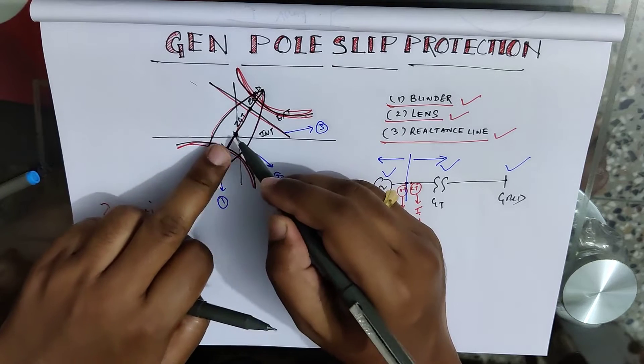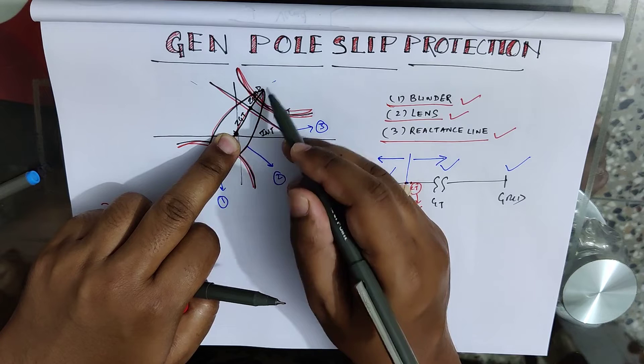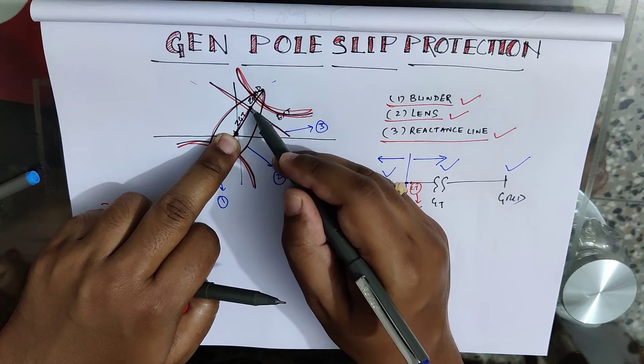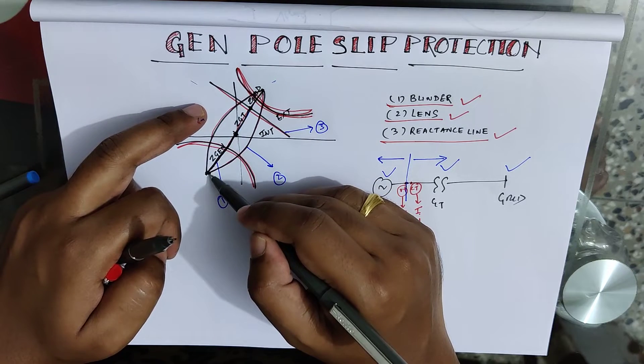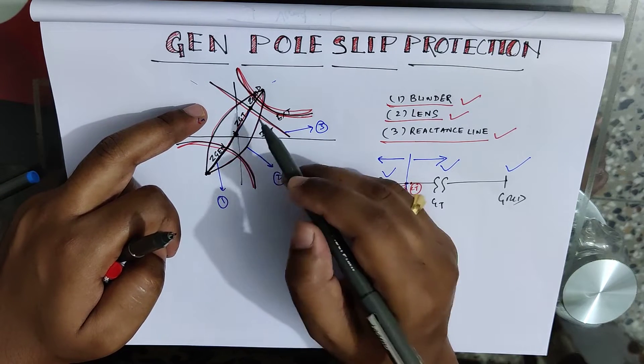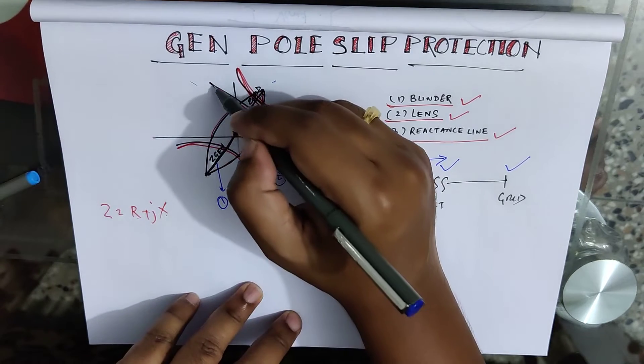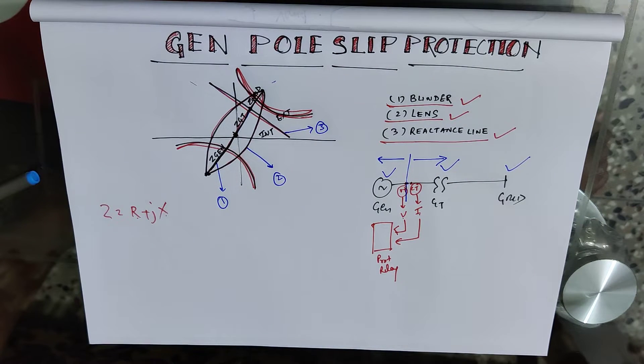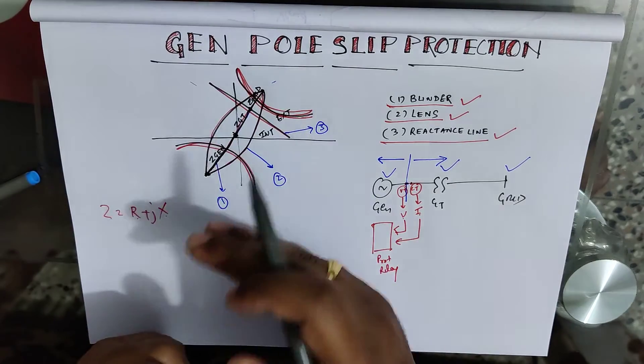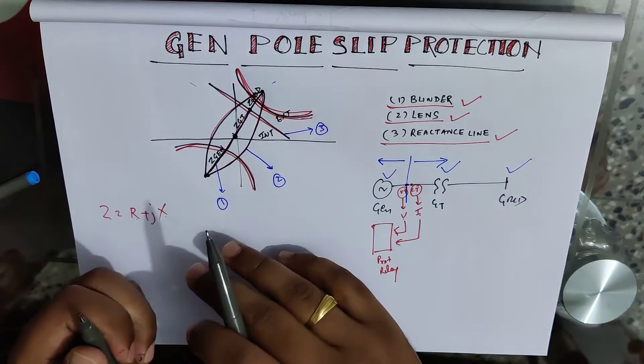At the terminal point, the relay in the forward direction will sense GT impedance and grid impedance, and in the backward direction it will only sense generator impedance. The intersection of GT and grid impedance — if we draw a line at that point — this line is called the reactance line. This reactance line divides the lens into two important parts: one is the external zone and the other is the internal zone.